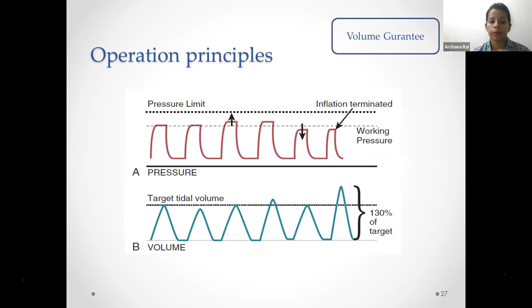Like we have discussed, it will sense from the previous breaths the pressure delivered and the tidal volume generated. But it is not that simple, because if the baby is having spontaneous efforts, it will be very difficult for the ventilator to sense how much pressure to generate. Here is the ventilator-given breath and these are the spontaneous efforts. So the pressures generated are very variable, and that's why the tidal volumes generated are very variable. Some ventilators like Drager use an algorithm in which it senses the triggered and untriggered breaths, like the spontaneous and the machine-induced breaths.